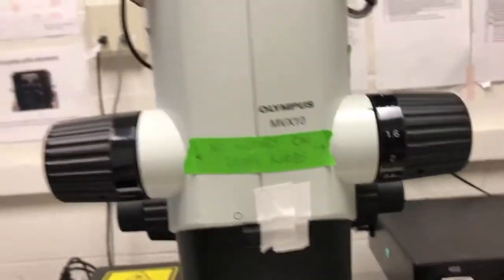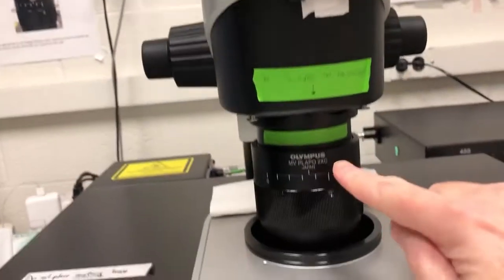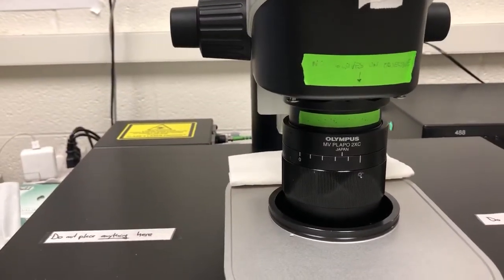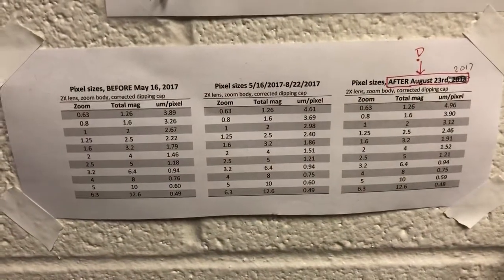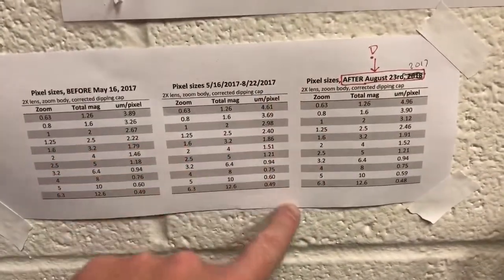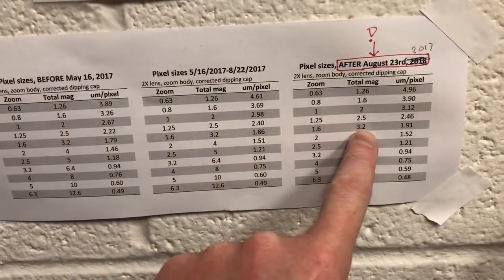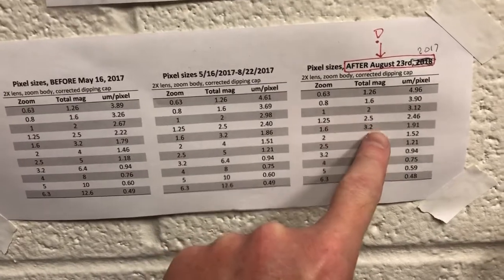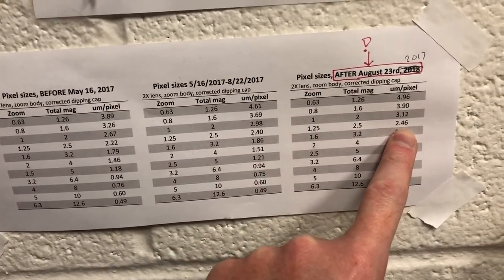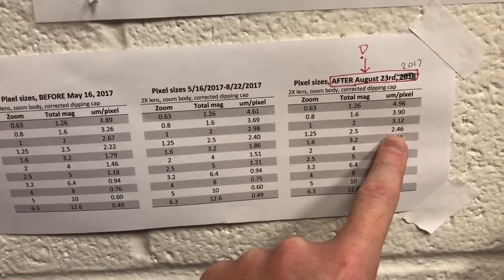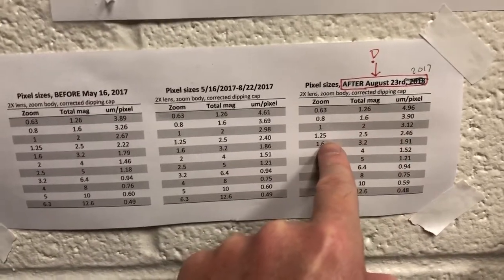That's the strategy we're going to use now. I've zoomed in by 1.25 on a 2x objective, so my effective magnification is 2.5x. More importantly than the total magnification is the pixel size. Looking at these tables of pixel sizes for different optics: with a zoom of 1.25 and magnification of 2.5x, the pixel size is 2.46 microns. Resolution on this system is roughly twice that, so I have around 5 micron resolution at that zoom in the XY dimension.